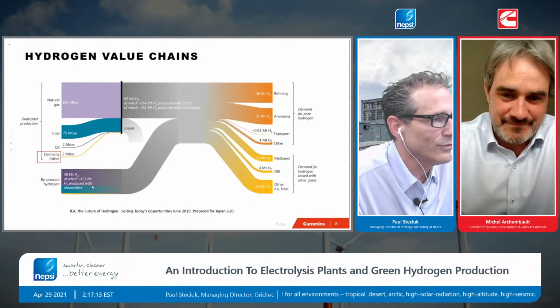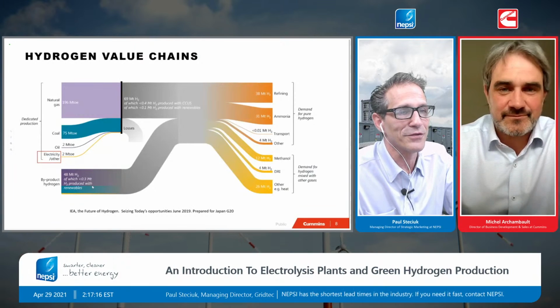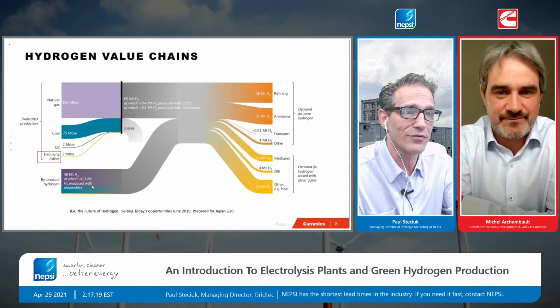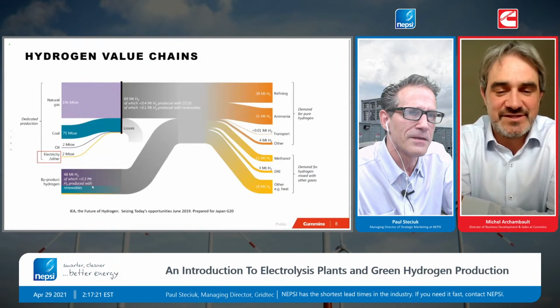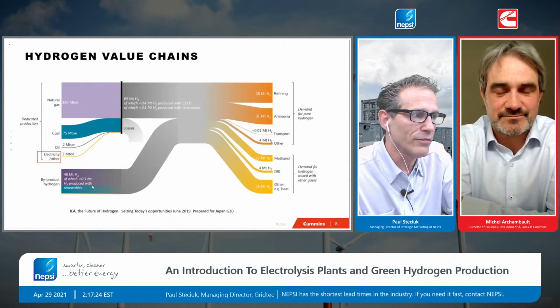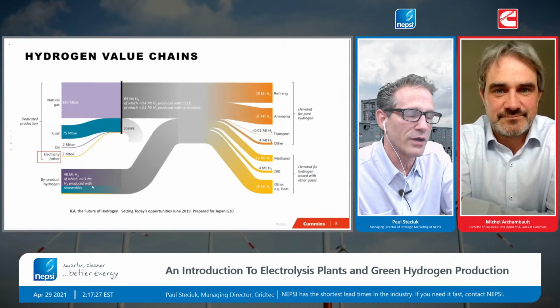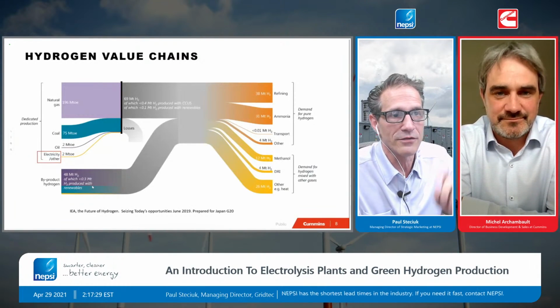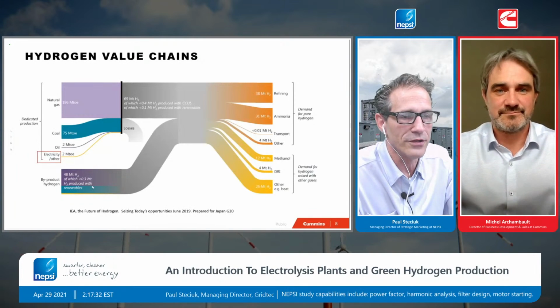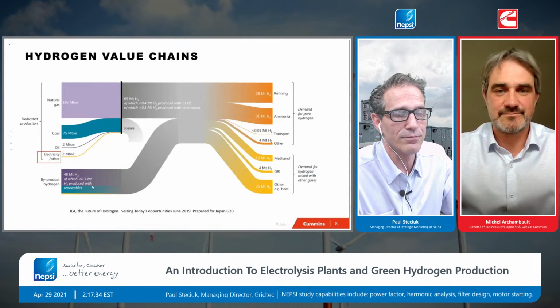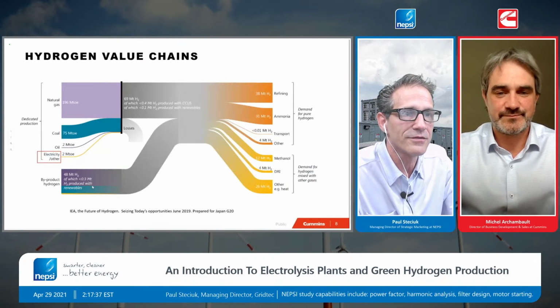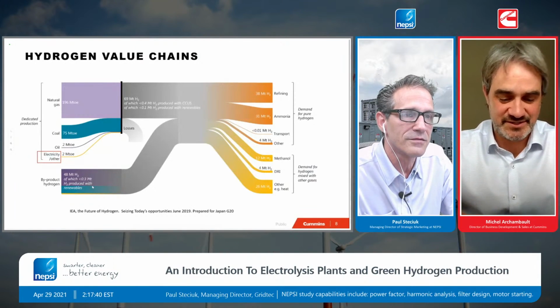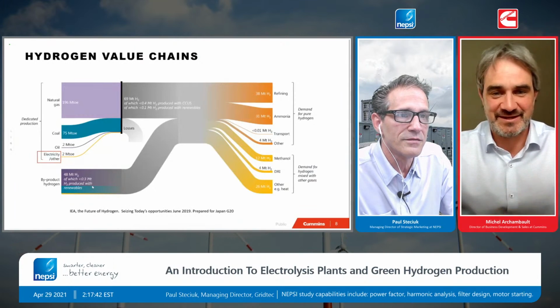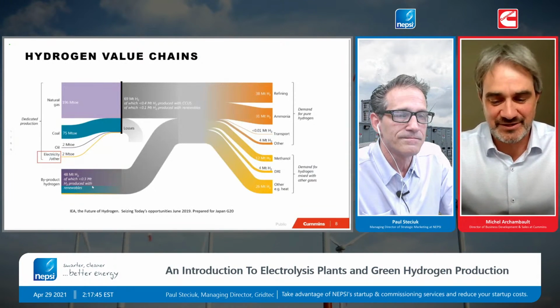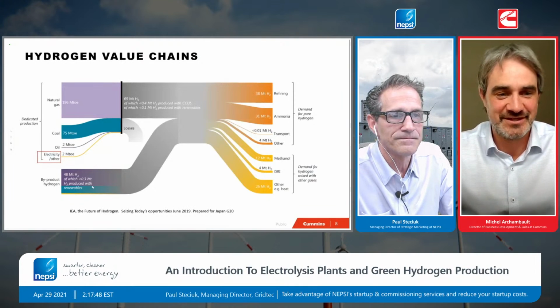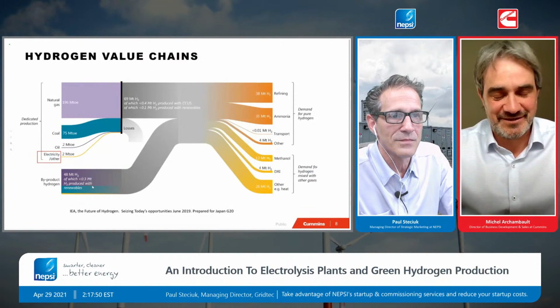Yeah, Michel, might I add that we often supply filters into that same marketplace, and the process is similar, right? And what is the size of these plants, Paul? The chlorine plants are typically in that 30 megawatt range. A rectifier feeding one cell line is about 30 megawatts, and sometimes these plants have multiple cell lines. It's an electrolyzer basically, but it's a different technology, with different electrodes. You're not splitting pure water, you're splitting sodium chloride brine. So it's very different technology, which has a different potential as well, cell voltage, I mean.